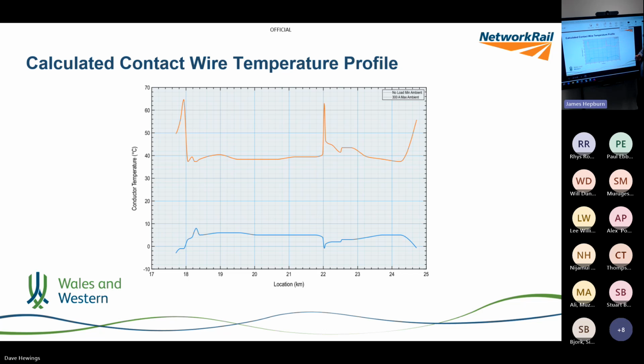So we've got a current flow there, 300 amps, and that comes back to our original starting point of what we're going to use the tunnel system for. We can then go from those ambient characteristics, albeit based on some early spot-location measurements - what would that mean if we transferred that, with that current, into the wire temperature? That takes us up a bit higher: we're now between 60, 70 peak and 40 degrees wire in that stable area.